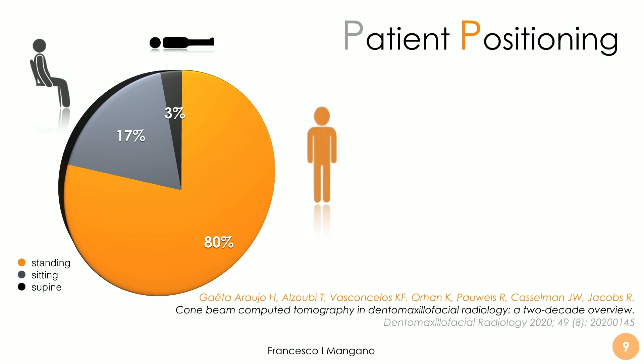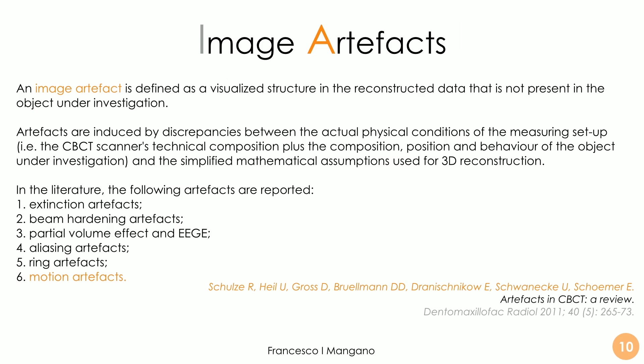Analyzing the literature, I found in a recent article that most CBCTs available on the market have the patient standing — in the classic position of the panoramic radiograph. In 17% of machines there is the option of having the patient seated, and only in 3% of machines the supine reclined position is available, so it's not so popular now compared to the beginning. The point is to avoid image artifacts. An image artifact is defined as a visualized structure in the reconstructed data that is not present in the actual object under investigation.